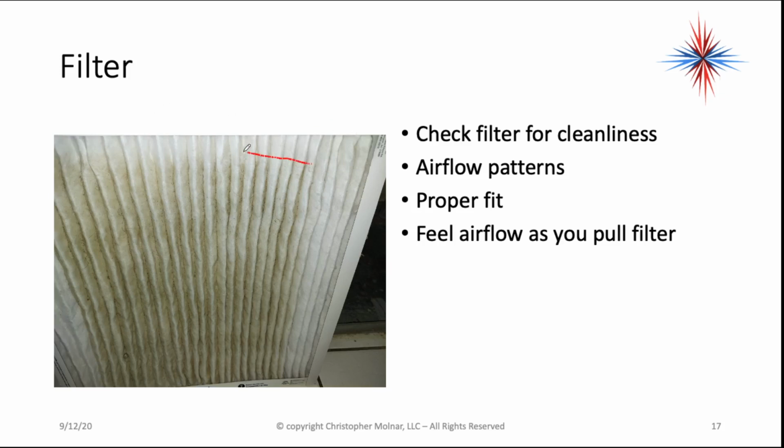But if you look at this, my airflow seems to be very concentrated to one portion of that filter. Is it the correct size? Well, still have to determine that. But it's not an even airflow straight across that filter. So my air is really just in the center of that.